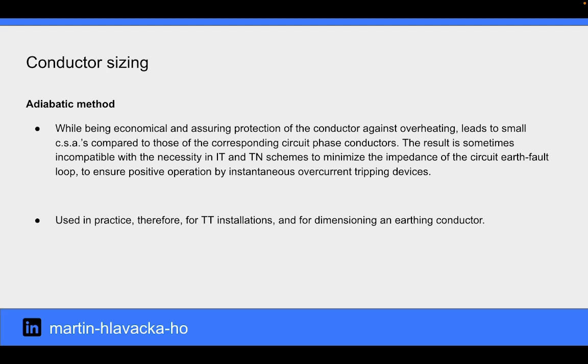The result is sometimes incompatible with the necessity in IT and TN schemes to minimize the impedance of the circuit earth fault loop to ensure positive operation by instantaneous overcurrent tripping devices. This method is used in practice, therefore, for TT installations and for dimensioning an earthing conductor.